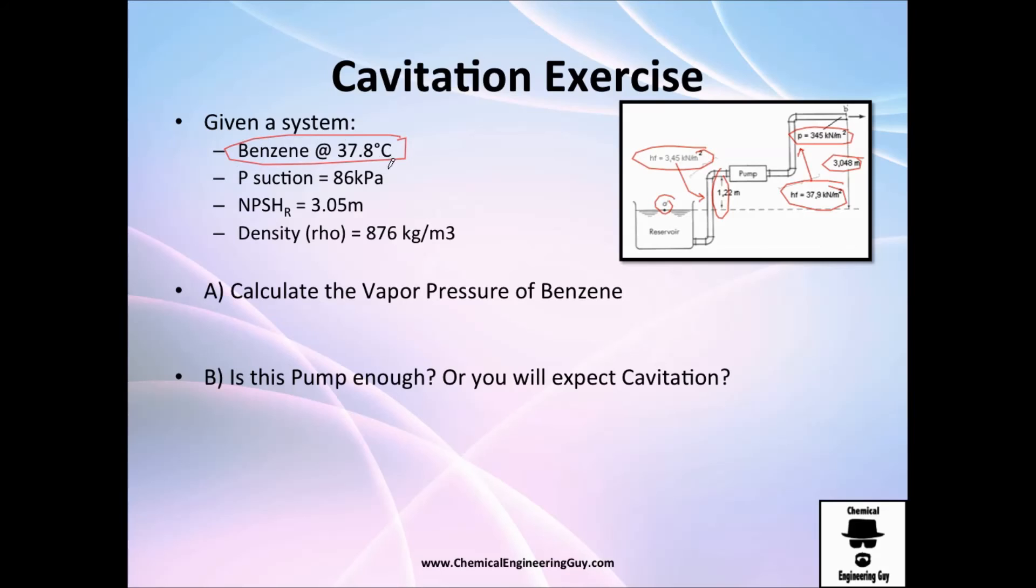They are very kind to give us the pressure in the suction line, which is interesting because normally they won't give it to you. Anyways, let's say this will always be the case. We have this pressure, pressure in the suction is constant, and the net positive suction head required for the operation of this pump is 3.05 meters. The density of this fluid, benzene, is 876 kg per cubic meter. So they tell you to calculate the vapor pressure of benzene, and once you have that, is the pump enough or will you expect cavitation?